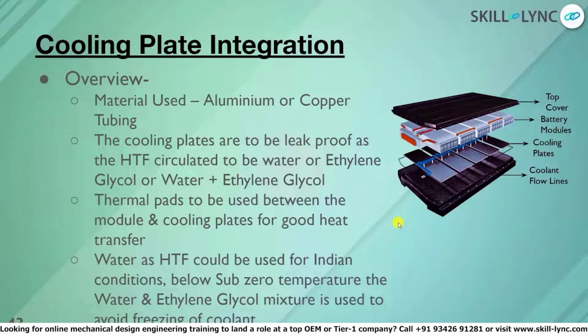So when water is going through, there should not be any leak, and if such leaks happen inside, there could be a catastrophe created as the coolant reaches the busbar high voltage connections, and that's the end of it. So it's very important to make sure that the cooling plates are leak proof. We also need thermal pads between the cooling plates and the modules, so that the heat generated by the modules is dissipated as much as possible.